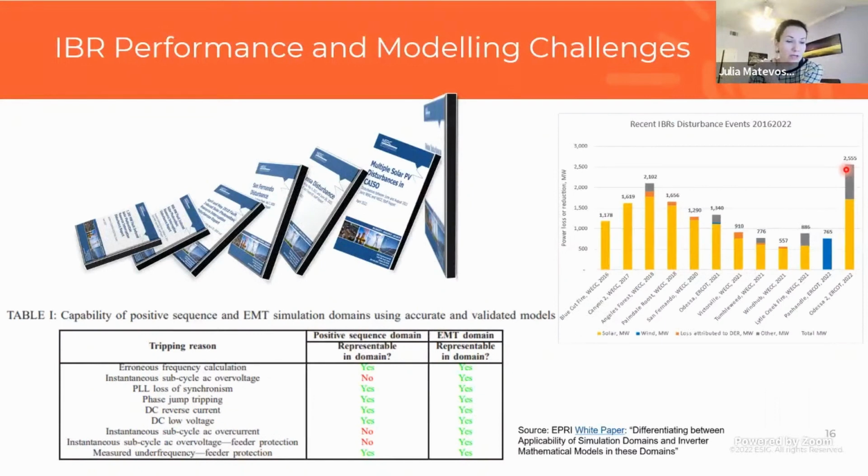And as I mentioned, currently inverter-based resources are required to stay connected during faults, but they still do disconnect. And so the problem then in the event analysis is to understand why this is happening. So they are not behaving according to requirement. Why was this not detected during interconnection studies, when the system operator investigated this generator during the interconnection process? Why was this not seen?